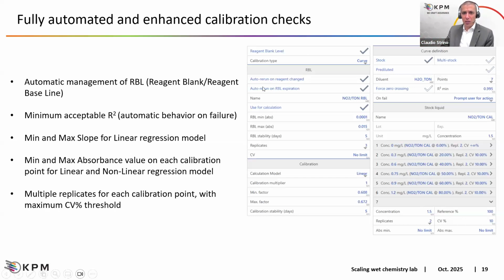Moreover, as we can see in the first two options for the RBL, we can have the automatic rerun in case of reagent changes, because we spoke about multiple reagent bottles, but the color of the reagent could be different. One typical example is the NO2 reagent that could change from transparent to dark pink over time because it is light sensitive. And when it is too colored, it is losing sensitivity. And in any case, the bottle in use could be a bit colored while the brand new bottle is fully transparent.